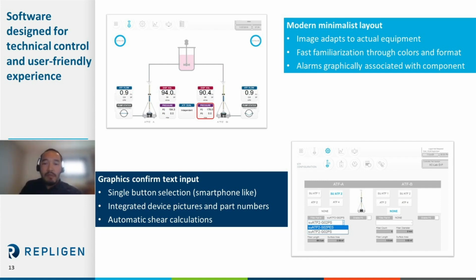On this example of the main screen on the top left, you see 2 ATF devices connected to the same bioreactor. Notice that the ATF images are the actual equipment being used. In this case, you know that you're using 2 single-use ATF2s. Here, it's kind of hard to see, but pump status actually shows an accurate representation of the diaphragm position during the diaphragm stroke. These strokes can be independent or synchronized in either of 2 modes. So if it's an in-phase sync mode, the diaphragms of both ATFs are moving up and down simultaneously. If it's an out-of-phase sync mode, the diaphragms are moving in opposite directions. And this mode can be useful, keeping constant working volume if you're using 2 ATFs, for example.